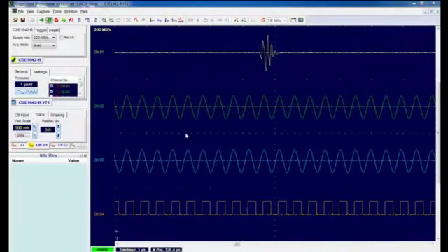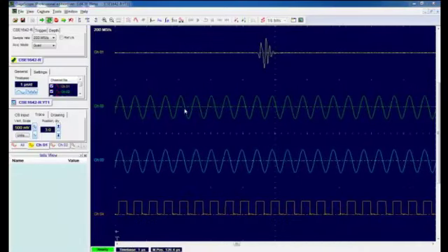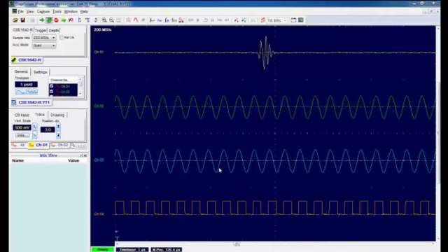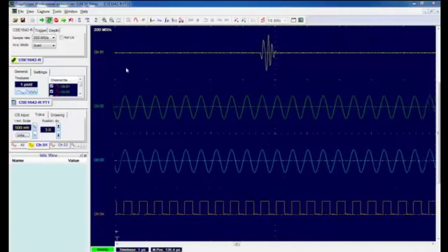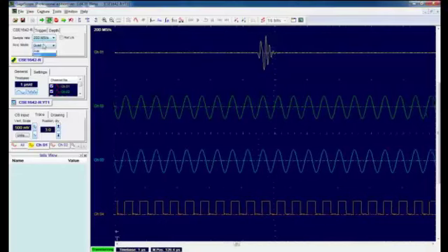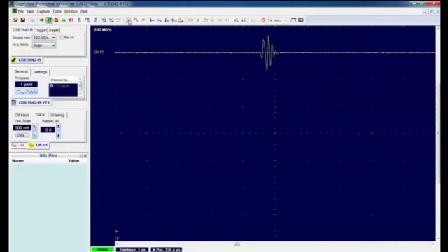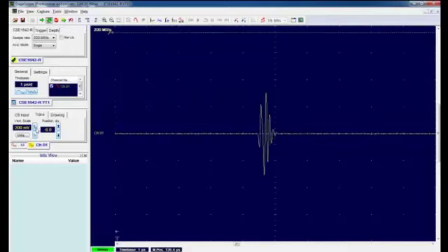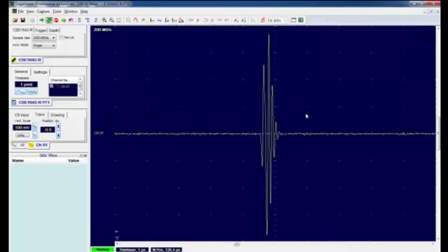Here we see GageScope capturing 4 signals from the FCI-X. As you can see, channels 2 through 4 are capturing simple sine and square waves, but we're interested more in the ultrasonic signal on channel 1, so I'll zoom in on that. Now, if you recall, this echo is received by the transducer after the sound bounces off the ultrasonic mirror formed by the surface of the water. And because the aquarium is currently still, this echo is very stable in position and amplitude.